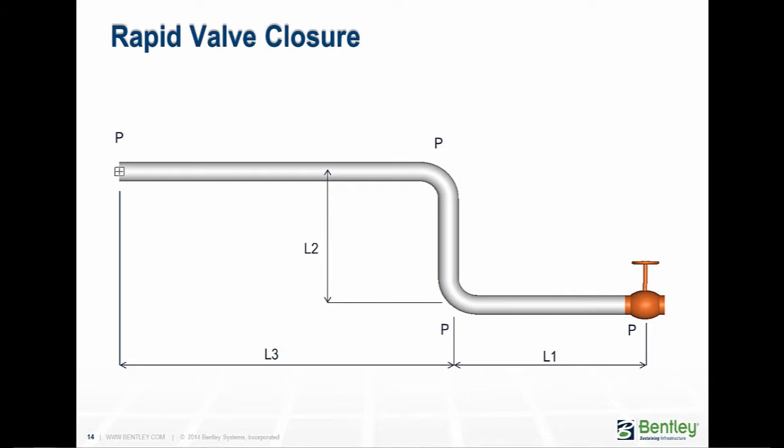The magnitude of the force in each of the pipe legs is dependent upon the time taken for the wave to travel between the bends, and unless these bends are very far apart, as with cross-country pipelines, or the valve closure is very rapid, the maximum force produced from 100% of Joukowsky's pressure rise will never be reached, as there is insufficient time to build it up.